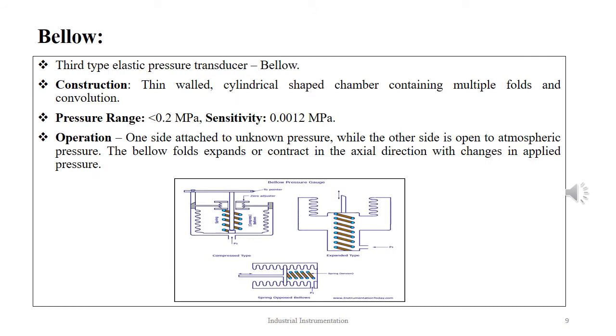The third type in the family of elastic pressure transducers is the bellow. The bellow elements are thin-walled, cylindrical chambers containing many folds and convolutions. The bellow is a one-piece expandable and collapsible, axially flexible device. With the application of pressure, the bellow gets deformed in the axial direction by either compression or expansion.